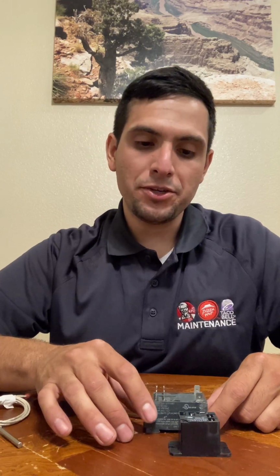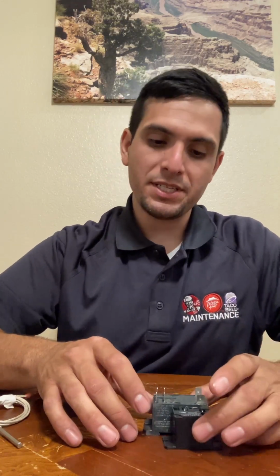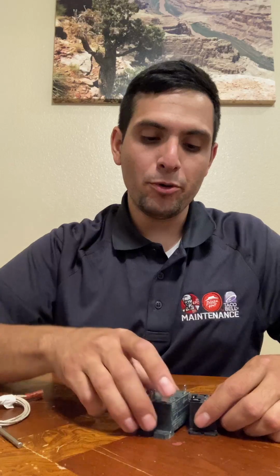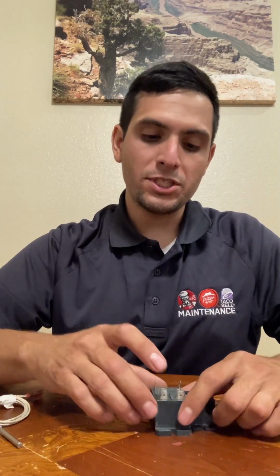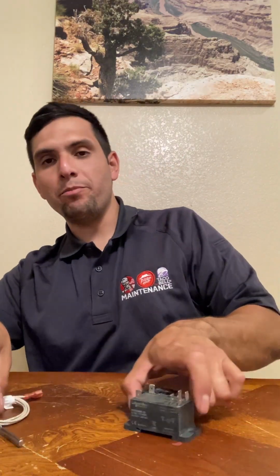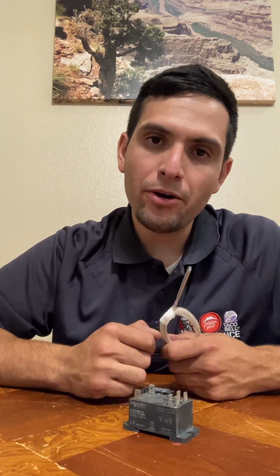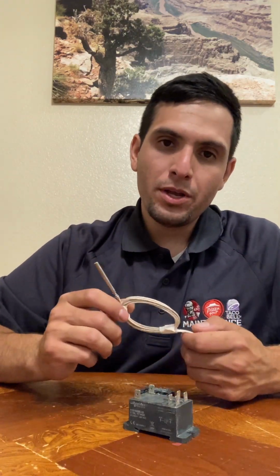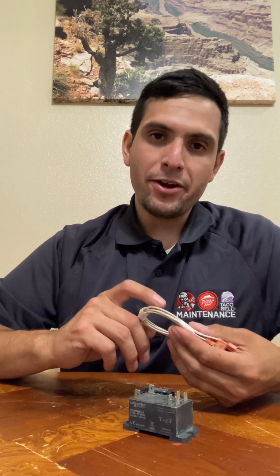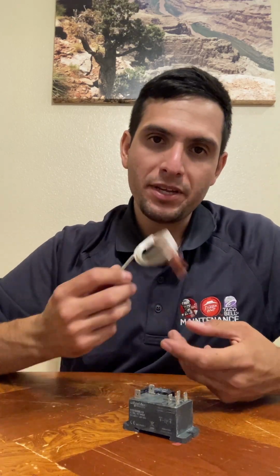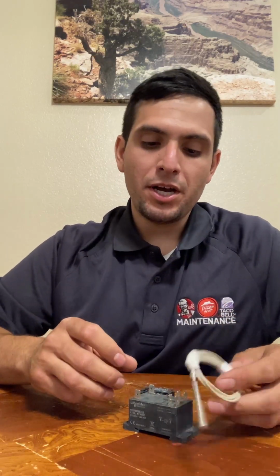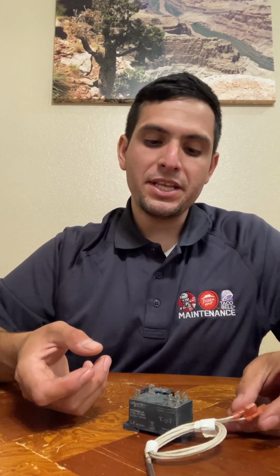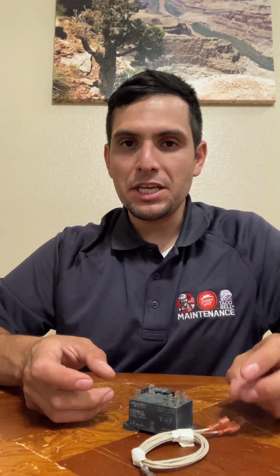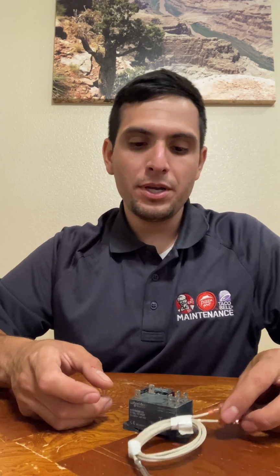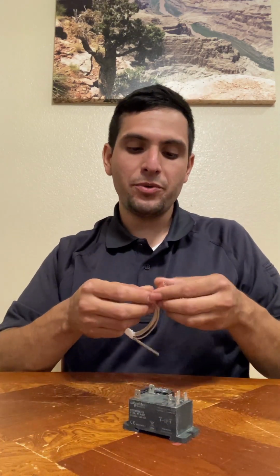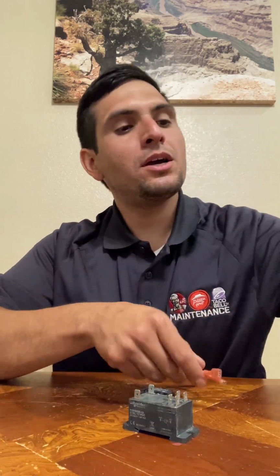And then obviously your transformer is what's going to send your low voltage to your board. So we'll start with, say you have a probe 1 error on there. So if you look up the manual or the wiring diagram, or you screenshot the mapping that I send everybody, if you see a probe 1 error, you'll see that it's going to be terminals E1 and E2 on your board.